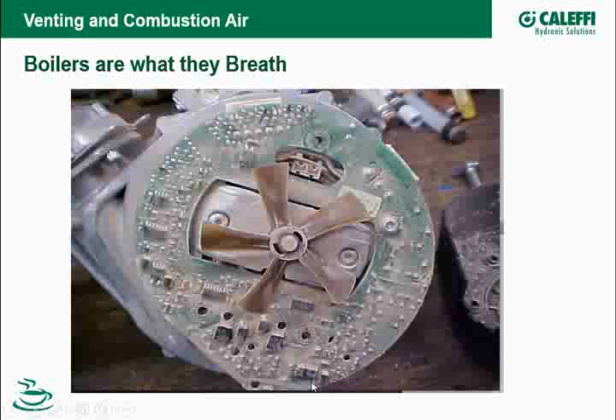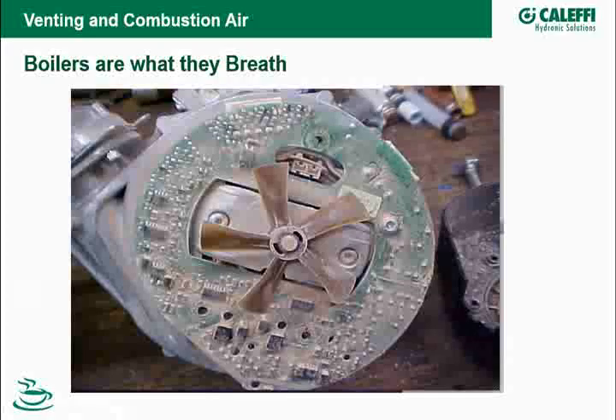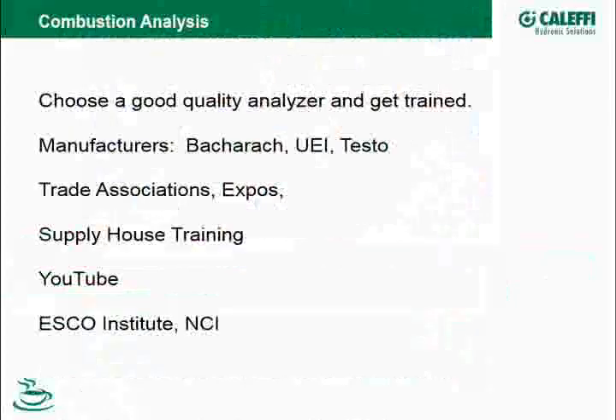So this little microprocessor-controlled fan inducer, which is for the gas valve here, was just, you can see the whole printed circuit board was covered with dust. This had to be replaced. So pay attention to those things too. It doesn't specifically have to do with the fluid or the hydronic side of the system, but certainly that's not something you want to fail in the middle of the winter time, especially if you don't have another one along with you. So look inside the boiler, take covers off on blower motors and stuff like that. See if there's any dirt and debris that you can blow out of there with an air hose or something when you're there.